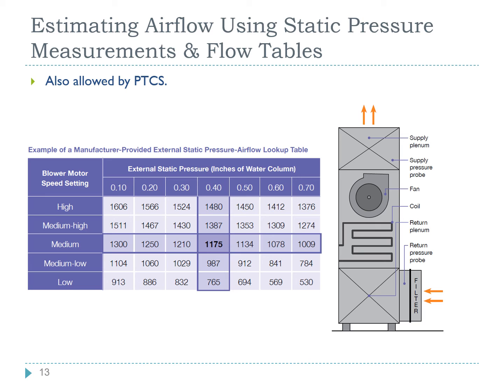Estimating airflow using static pressure measurement and airflow tables. So here's an example of an airflow table below. It's used by measuring the external static pressure of the system. You measure in the supply plenum and then on the furnace side of the filter to get your external static pressure. You determine what the blower motor speed setting is, and then you can cross-reference that on the table to get a CFM. That CFM can then be divided by the tonnage of the outdoor unit to get your CFM per ton.